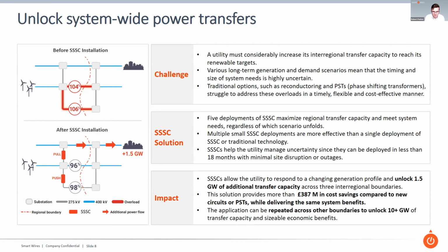And the impact that this set of SSSC installations had overall was to increase the transfer capacity across a number of different boundaries by 1.5 gigawatts. That effectively amounted to about 387 million pounds listed here in savings passed to the customer in reduced congestion costs. And the advantage was that once this solution was employed once in the existing grid, it could be applied multiple times around the grid, because there are multiple locations where this boundary condition exists, where there's a limit to the amount of transfer capacity going across those boundaries.